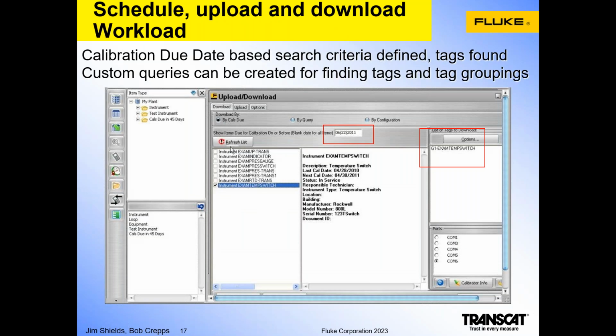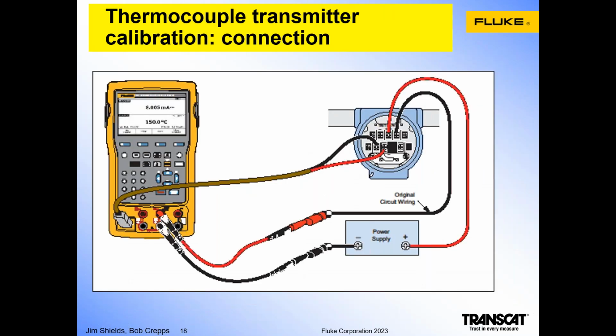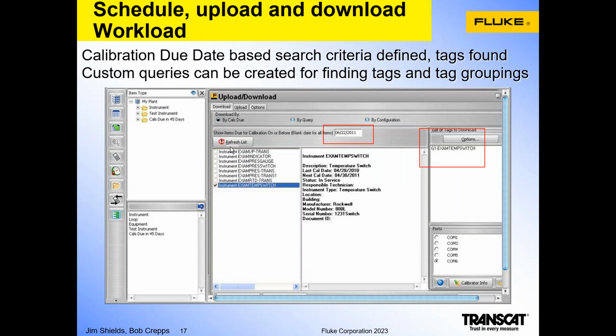Now here in the software, based on a variety of different factors, you can select based on date-based criteria, or you can look for other various elements in the plant using a query. For example, I could look for all tags due before this date in one section of the plant that are pressure devices, identify those devices, and then put them in the load list to load the calibrator. Then I load those into the calibrator, and then we go to the field to perform the calibration.